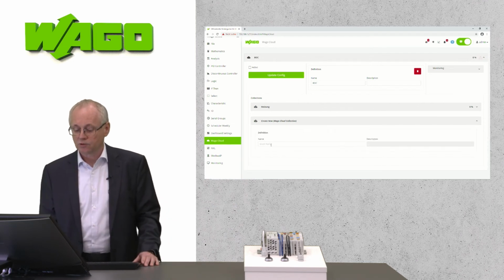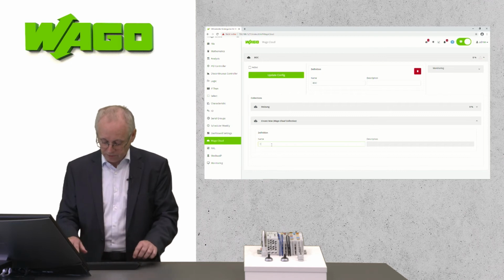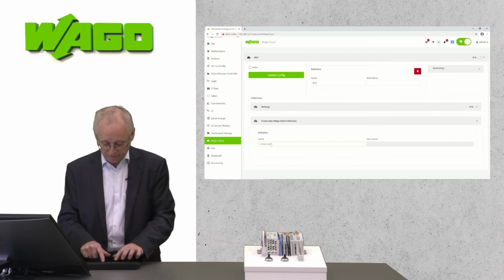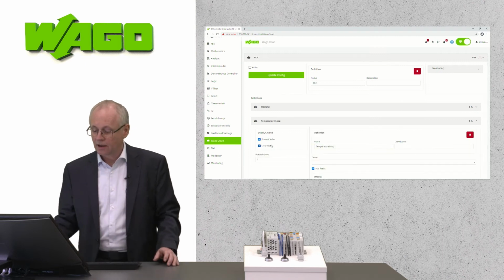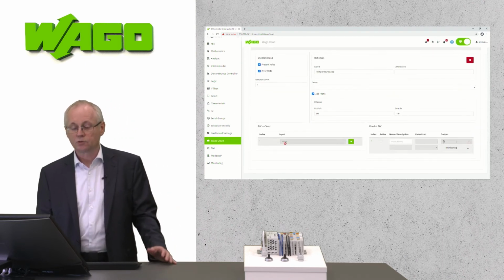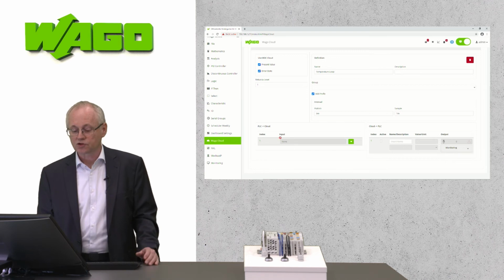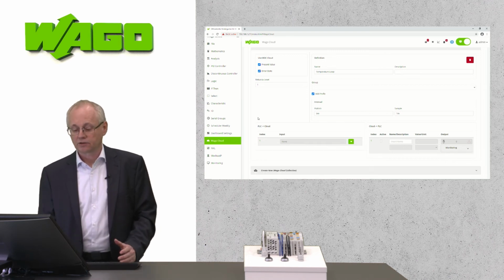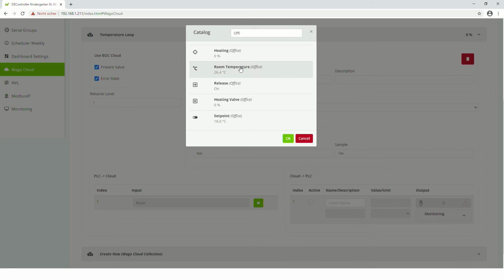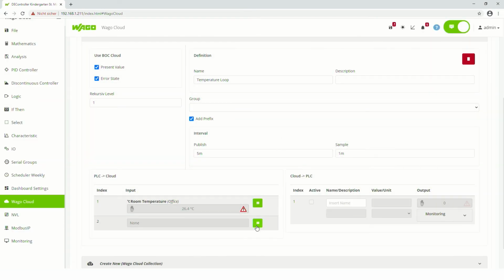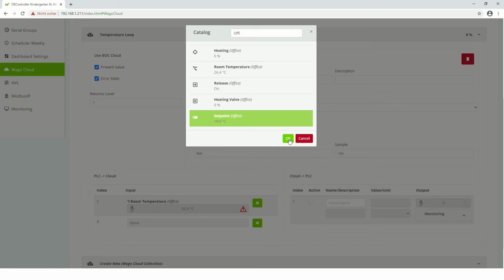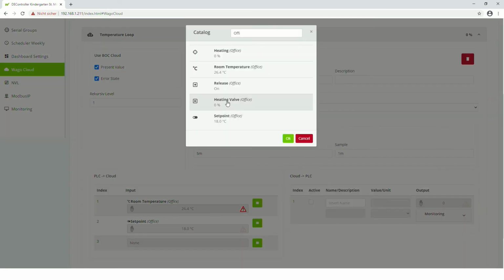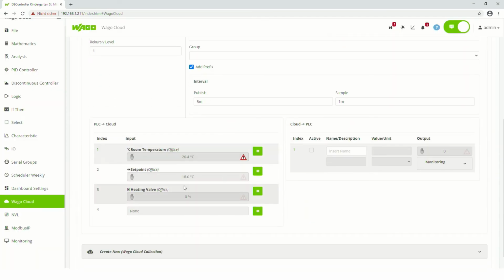So I will create a new collection and assign a name. Now you have the possibility to define the data points which should be connected from the controller to the cloud. Again we use the data point catalog, selecting the room temperature and the set point, for example, maybe also the heating valve. These data points will be sent from the controller to the cloud.